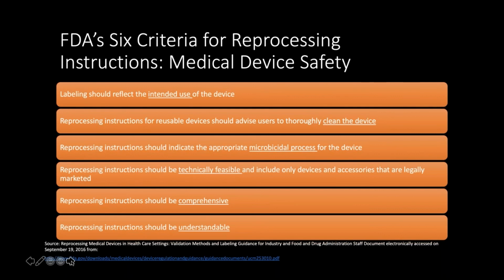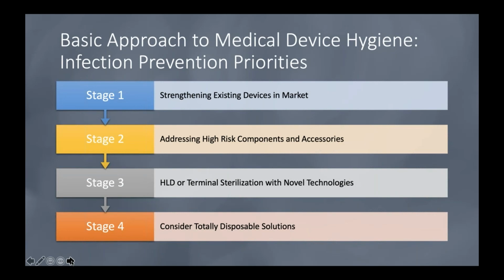And so we've got to figure out ways to make things extremely user-proof and bring it down to the level of the least common denominator for patient safety. So from that, there's really 4 different ways that I can think about as to how we get there, right? How do we get to that point of true patient safety? The first is to look at the devices that were already out there. And so pretty much everybody's done this, where the different reusable manufacturers said, we got to strengthen our product, we got to make it better based on this data of contamination. The second piece that FDA called out in their safety alert was, what do we do about high-risk components like the elevators, right? Those distal ends and the elevator channels where we know that there's been recovered microorganisms that are problematic.